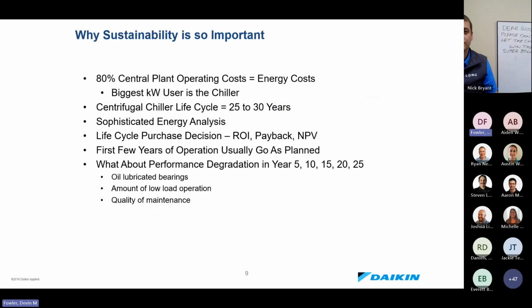So why is this sustainability so important? Why do we really push on our efficiency and the lack of losses in the system? About 80% of your chiller plant operating cost every year is going to be your energy cost, and the largest user of that energy in your plant is going to be your chiller. These chillers will be operating, we know, with a life cycle of anywhere from 25 to 30 years, with modern machining and modern practices in building these chillers and the controls that we have.